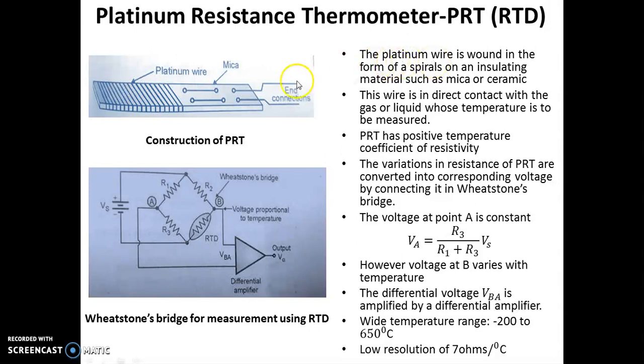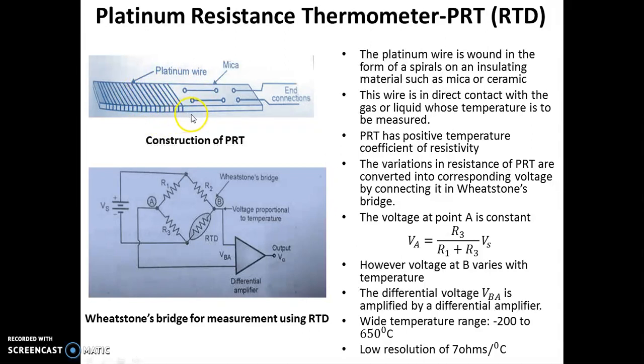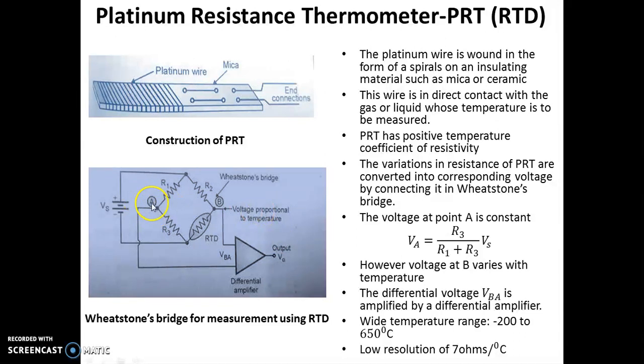The platinum wire is wound on a ceramic or mica material. This wire is in direct contact with the liquid or gas whose temperature is to be measured. PRT has a positive temperature coefficient of resistivity. The variation in resistance of PRT is converted into corresponding voltage by connecting the PRT in a Wheatstone bridge. The voltage at point A is constant and is given by VA = (R3 / (R1 + R3)) × VS.